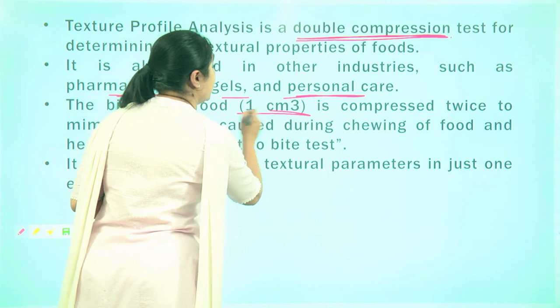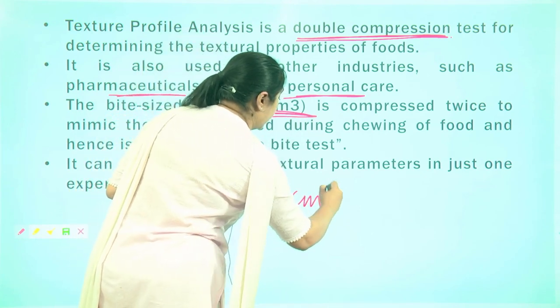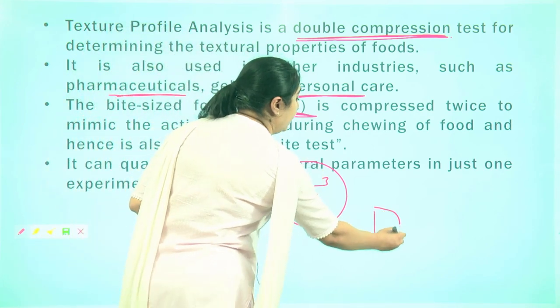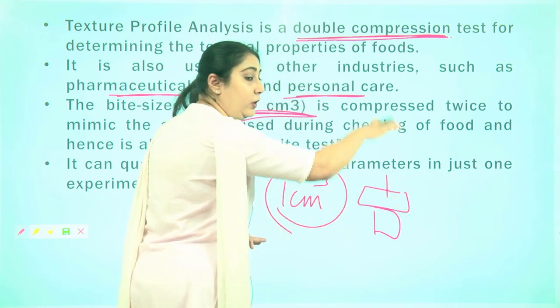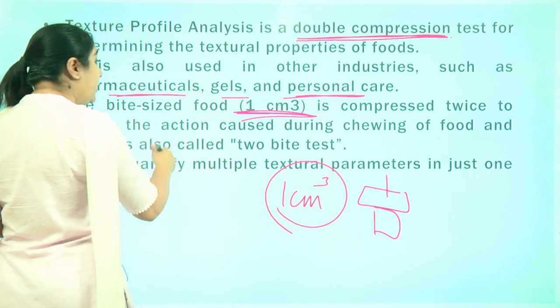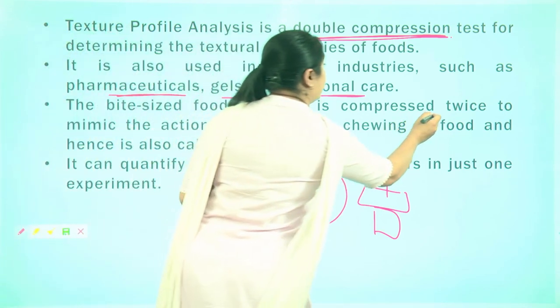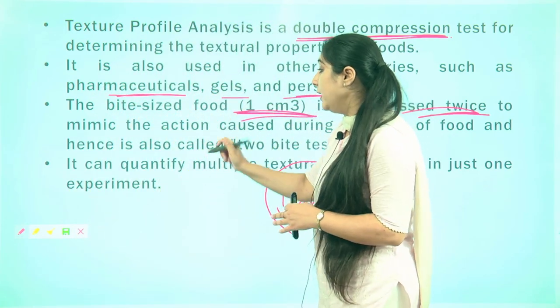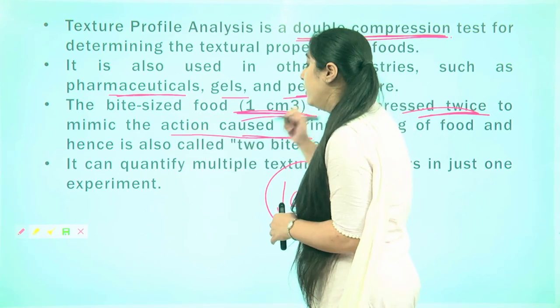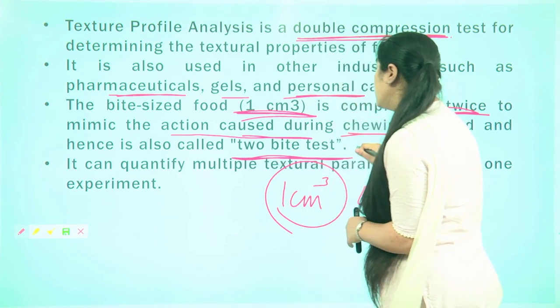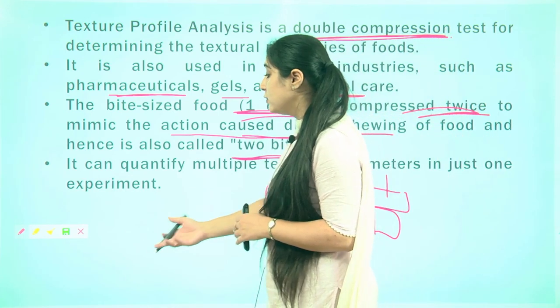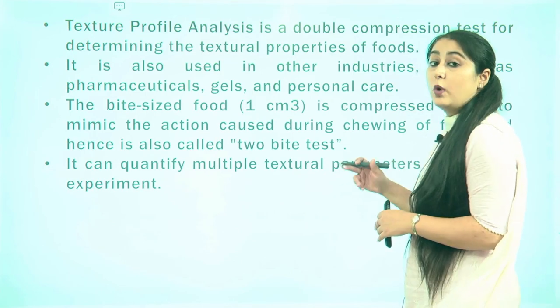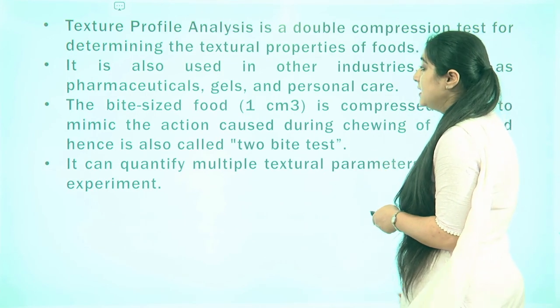A bite-sized food material — generally around one centimeter cube — is placed in the equipment and compressed twice. The motive of compressing the food material twice is to mimic the chewing action of the teeth. It is also called a 2-bite test, and the main advantage is that it can quantify multiple textural parameters in just one experiment.